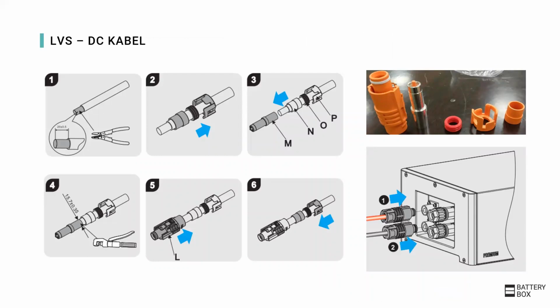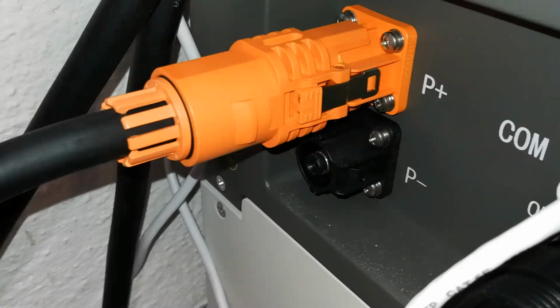For the DC cable connection, the LVS has a special DC connection strategy, which allows to connect the DC cables without opening the battery and still allows for a high protection level of IP55. Therefore, a special LVS DC male connector piece has to be attached to the external DC cable. The LVS DC connectors have to be ordered for the selected cable size and can be crimped to the cable as shown on this slide. Also, pre-configured cables with the DC connectors already attached can be ordered. Then the DC cable connection is as simple as pushing the cable into the LVS PDU as shown here.